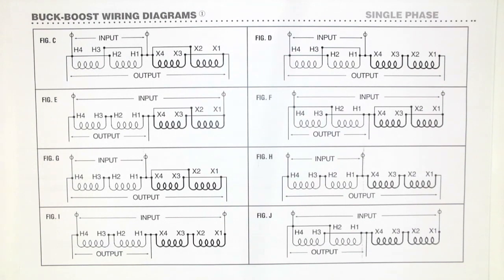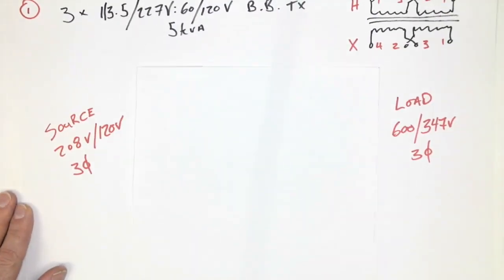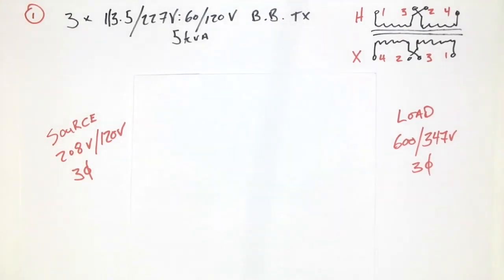Well, let's do a few examples with buck boost and we'll do some calculations and connections together. The first one we're going to do is a Y connection. The Y connection is going to use three 113.5 227 to 60 120 volt buck boost transformers. I've got the diagram of the transformer here, and it's going to have a rating of 5 kVA.